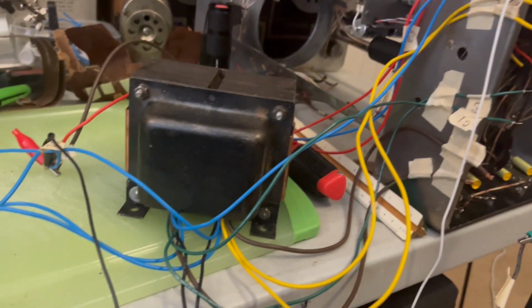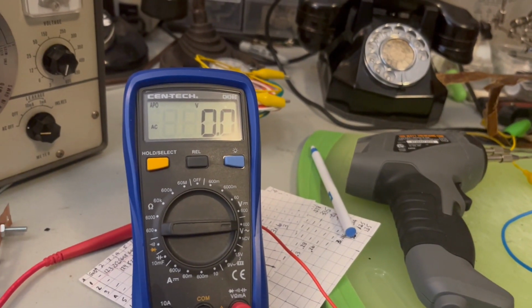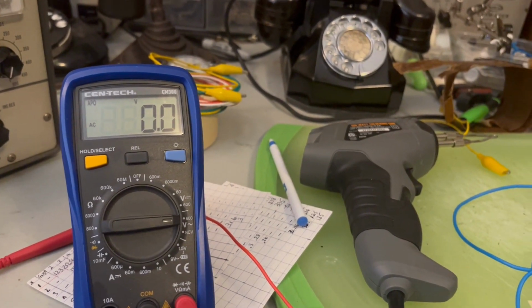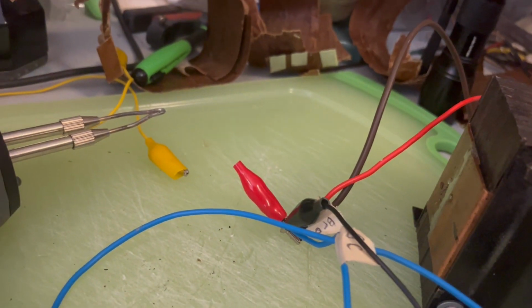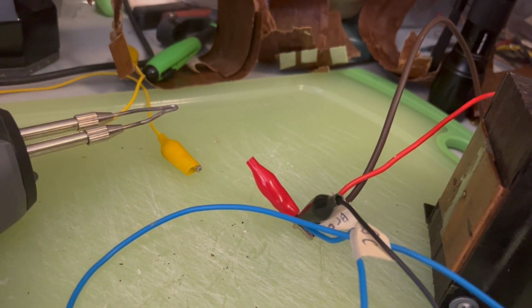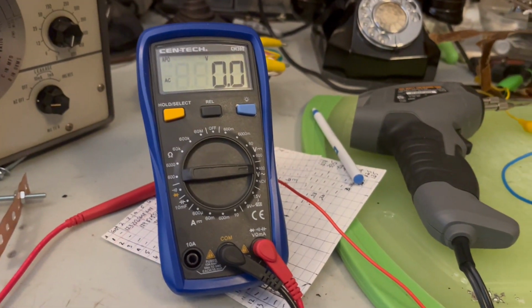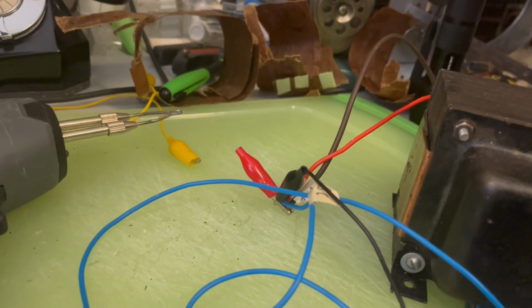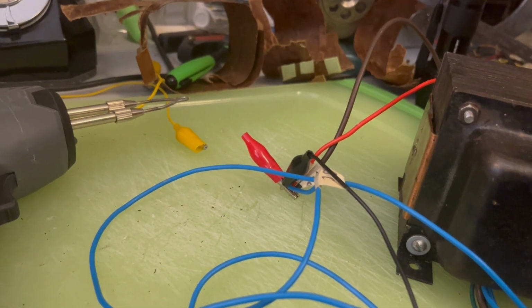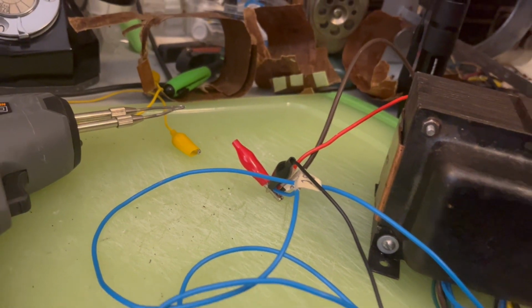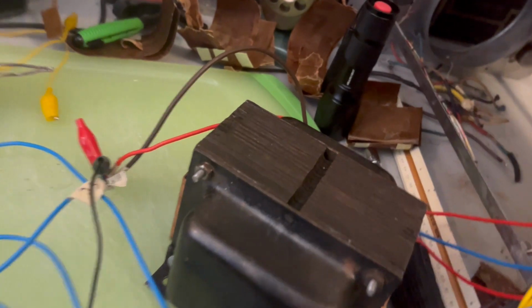First thing I want to do is make sure that it doesn't blow a fuse. And I've got a voltmeter set up here so I can take readings. So I'm going to start out. Right now I've got all 3 of the center taps wired together, and that's on my negative side of my meter. Ordinarily, what would happen is that if all 3 of those leads are wired together, the fuse would blow. So we're going to check that right now.